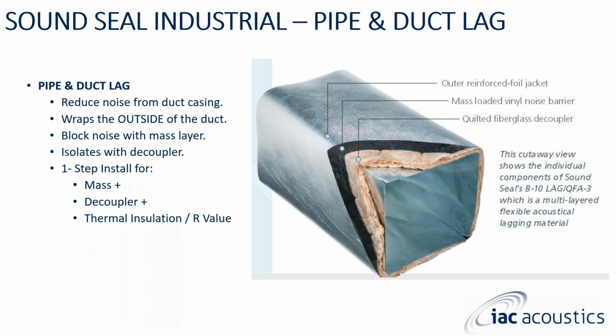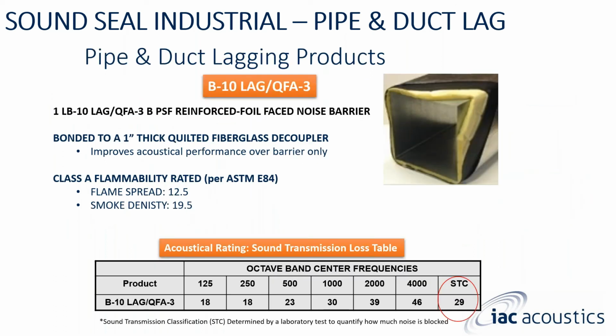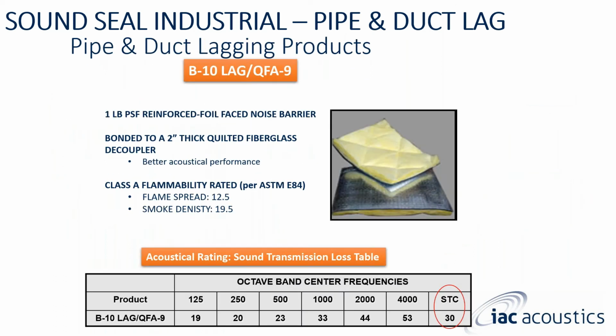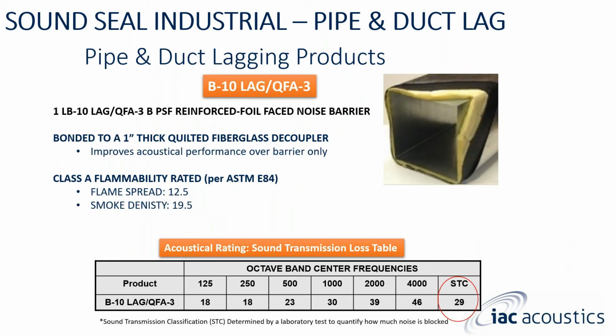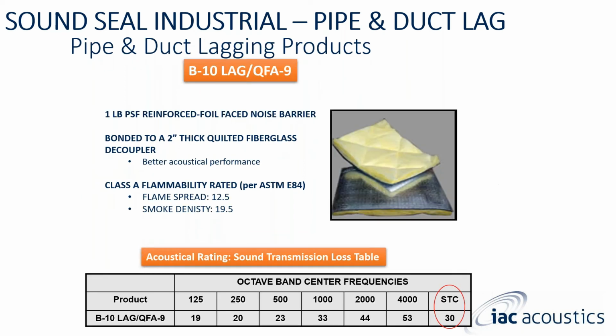Our sound seal pipe and duct lag material, you can see that this is wrapped around duct. You can wrap this around silencers. You can also wrap this around pieces of equipment. This comes in 54-foot rolls. It is an outer reinforced foil jacket with a mass-loaded vinyl noise barrier underneath, and underneath that is a quilted fiberglass decoupler. We can do this in a 1-inch thick quilted fiberglass decoupler or a 2-inch thick quilted fiberglass decoupler. You can see that it has really good STC ratings: the 1-inch at 29 and the 2-inch at 30.